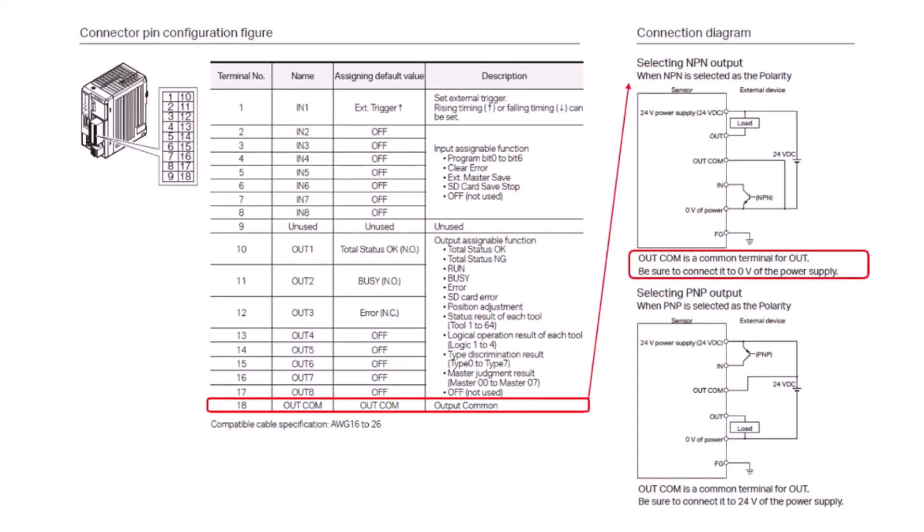If instead you want to use an NPN output for a 0-volt signal, your output common is going to connect to the 0-volt side of the power supply.